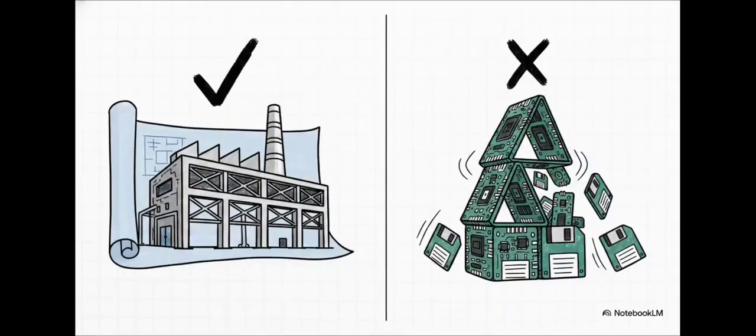So let's rapidly synthesize everything we've learned into the ultimate architect's checklist. 1. Default to a station-specific topology for maximum flexibility. 2. Never bypass the PC station when creating OS servers or clients. 3. Remember the wizard's blind spot and manually build your industrial Ethernet plant bus subnets. And 4. Vigorously protect the single master library as your only source of truth.